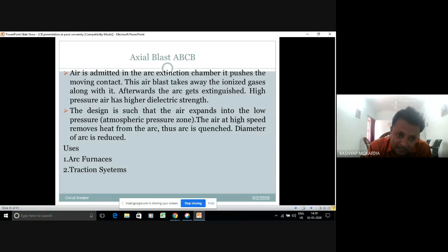It is used in arc furnaces and traction systems. In interviews, in industry, many times you will be asked about the application of the air blast circuit breaker, say the air brake circuit breaker. You will quickly say that it is used for an LT motor for 90 to 160 kilowatt rating. Starters. So it has an application. In the book, it is written that starters can be used up to 5 HP. But in industry, the starter can be used up to 90 kilowatt. But the source should be strong enough to deal with the problem of a voltage dip.